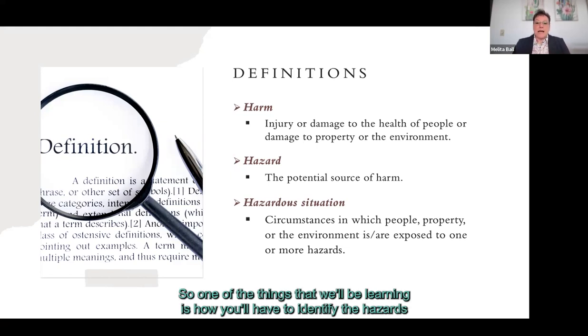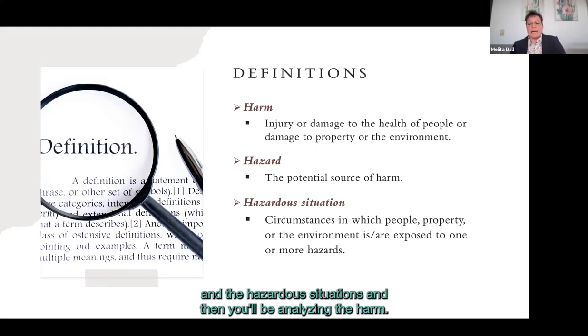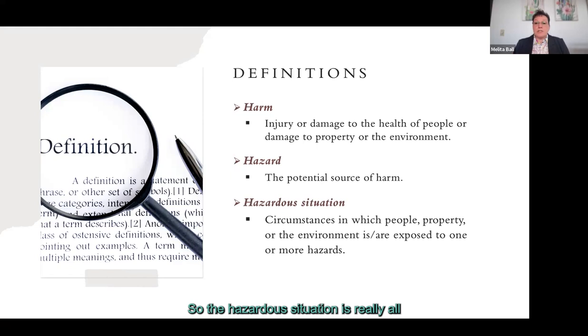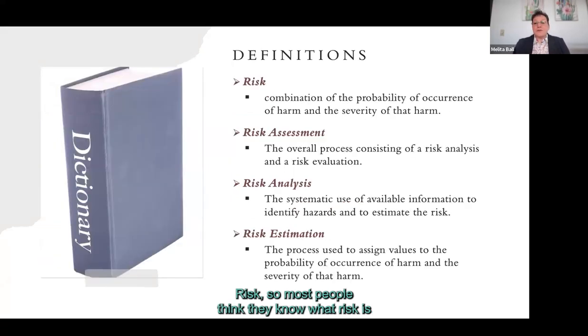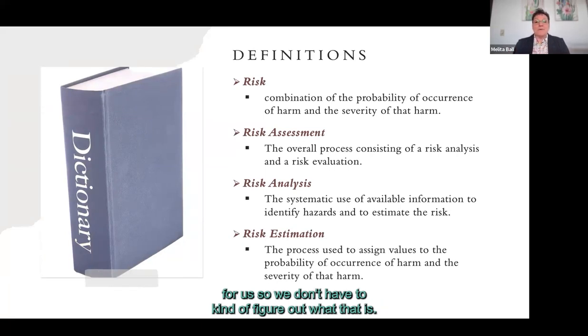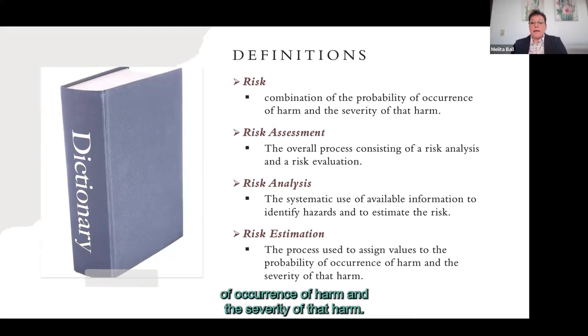A hazard is the potential source of harm. You'll have to identify hazards and hazardous situations and then analyze the harm — that's part of the risk management process. A hazardous situation is all those circumstances in which people, property, or the environment interact and are exposed to one or more hazards. Risk is defined by the standard as a combination of the probability of occurrence of harm and the severity of that harm.